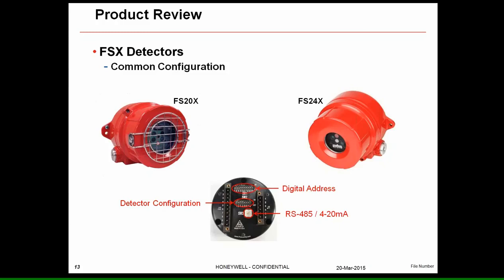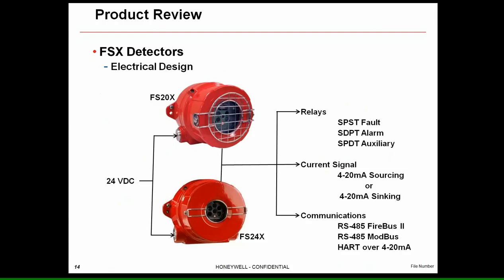The top 10-position DIP switch is used for a digital address — the first three positions are reserved for factory use, and positions four through ten give us a 7-bit digital address providing 128 unique addresses. The middle 8-position DIP switch configures the detector: latching or non-latching relays, normally energized or de-energized, verification time of five or ten seconds, and sensitivity settings — long range, mid-range, or short range. The rotary switch selects the RS-485 protocol mode and whether we source or sink current for the 4–20 mA output.